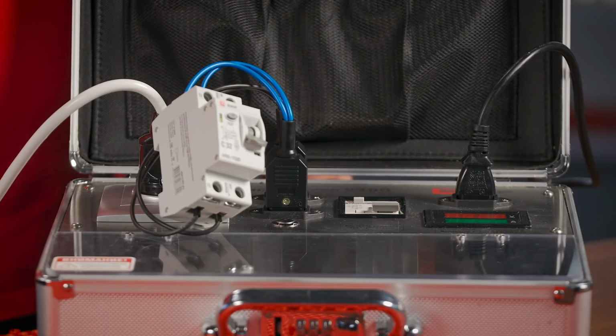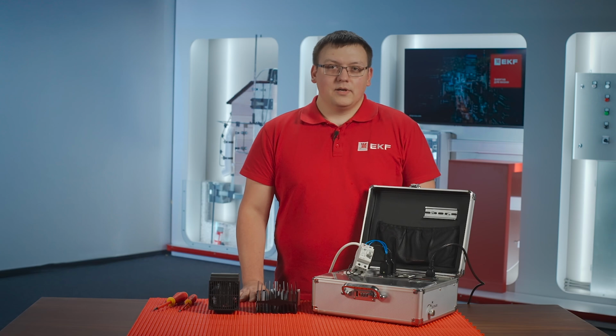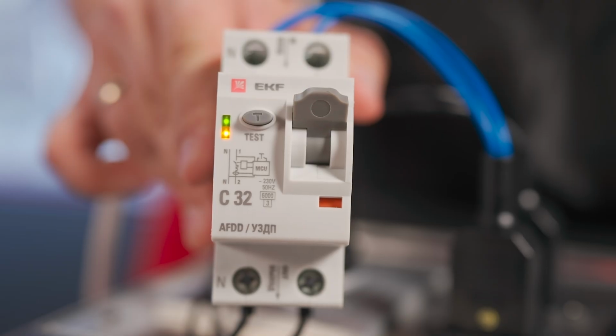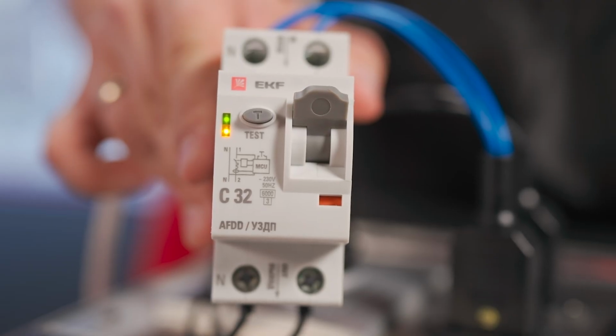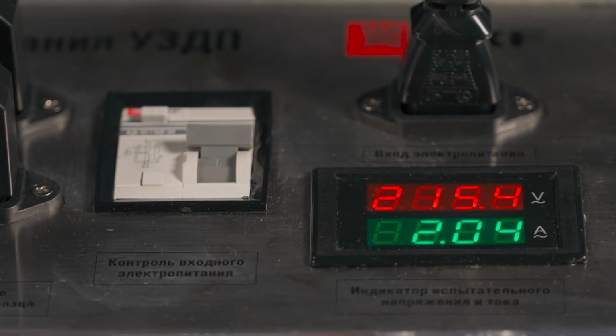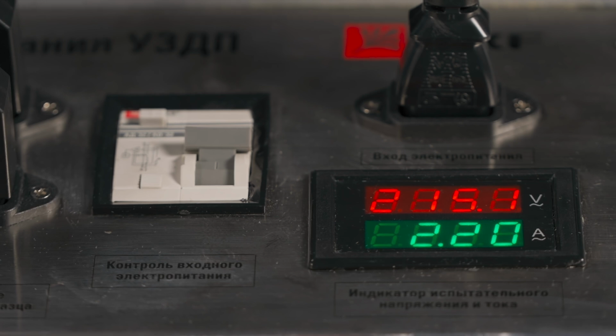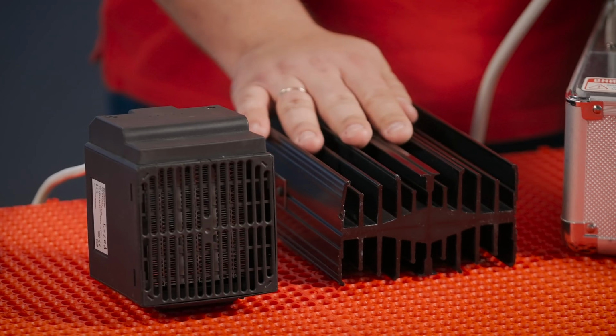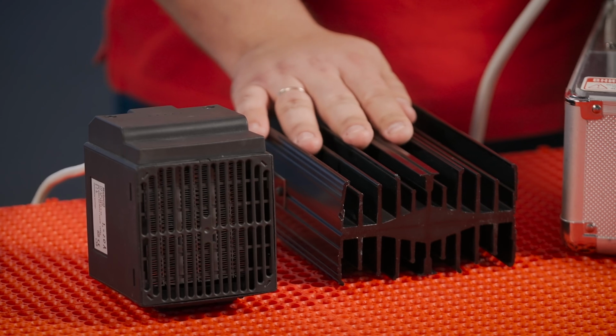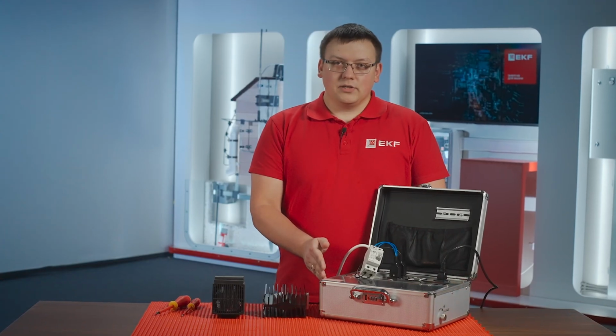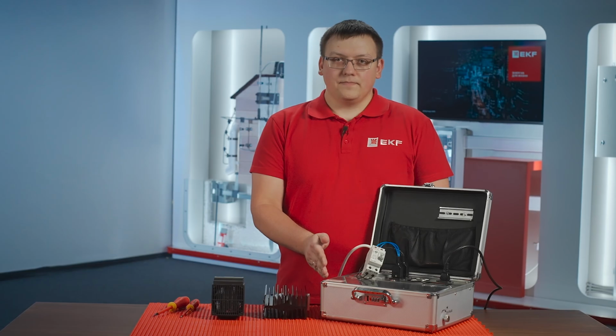Let's have a look. So here we have a test bench to check the correct operation of our AFDD. In this case, it's an AFDD rated for 32 amps, curve C, with a circuit breaker. We have a digital voltmeter and an ammeter that show us the circuit parameters, and a curve C 32 amp RCBO at the input. As a load, we'll use two electric single-phase heating elements connected in parallel with a total capacity of 500 watts and a rated current of 2.5 amps. And as an arc generator, we'll use two carbon rods.